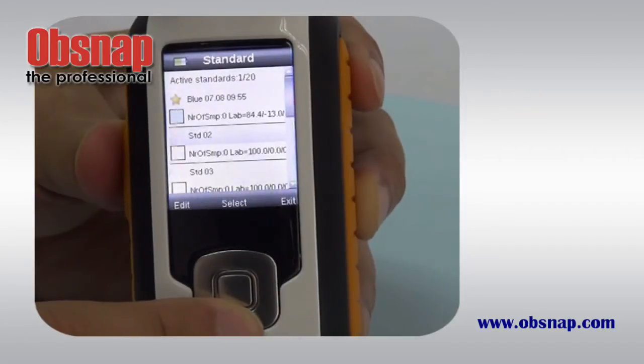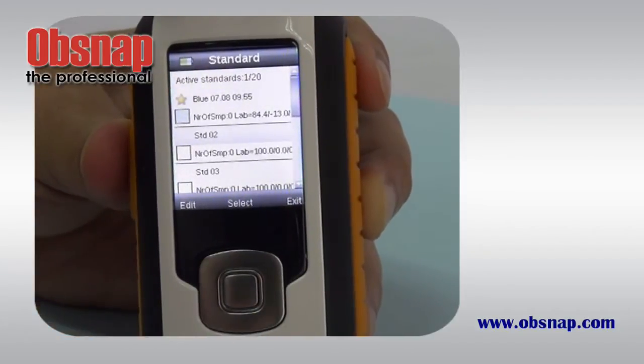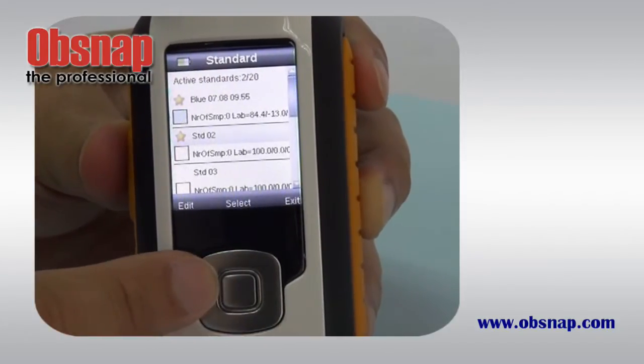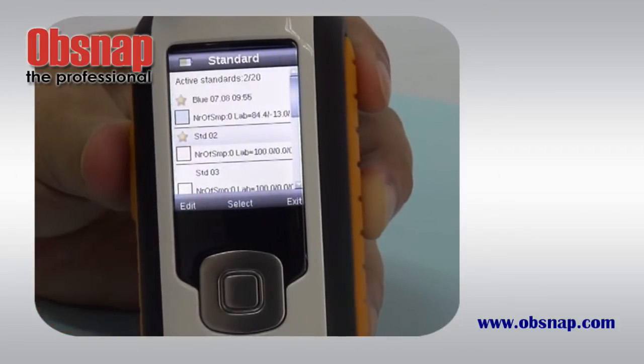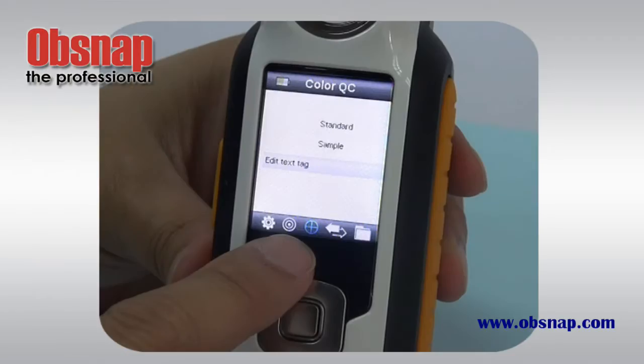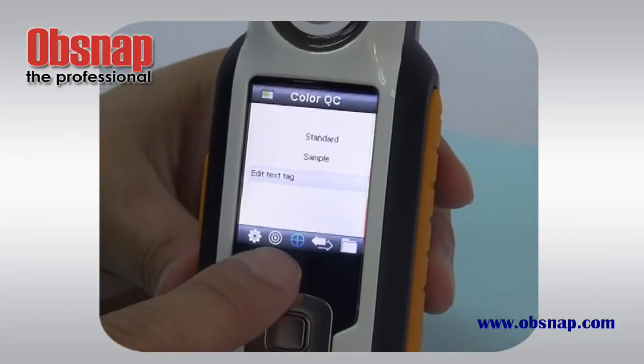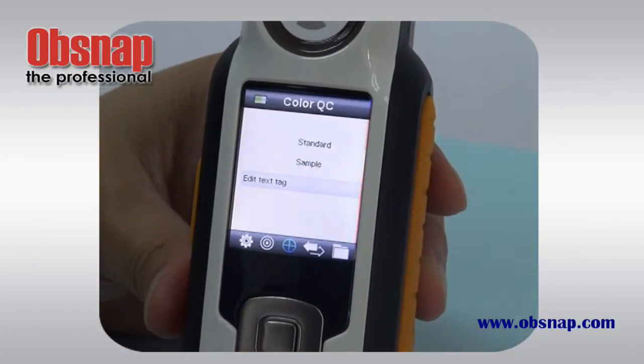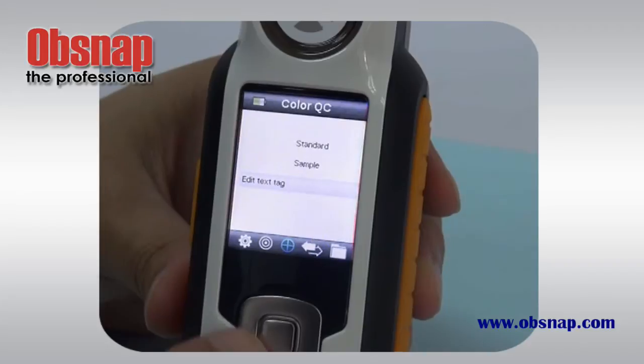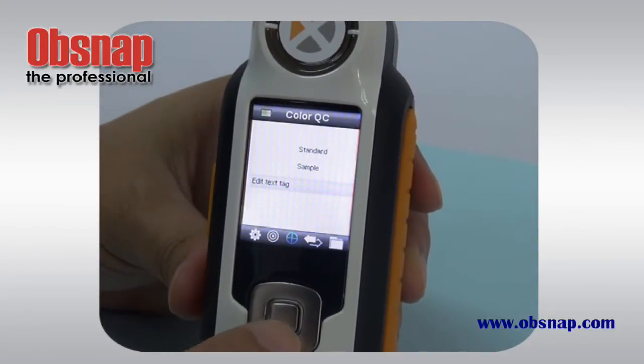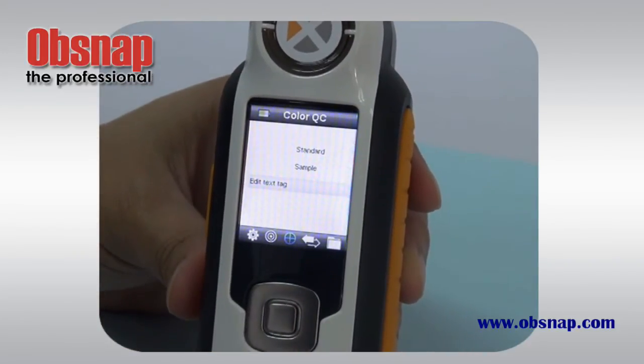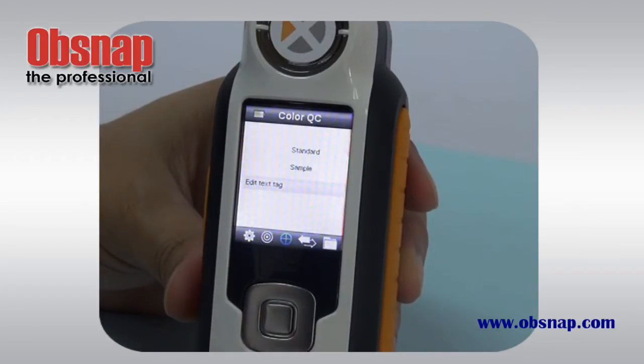For the subsequent standards you need to do, it is the same procedure: select it and then edit, and then you can measure onto the standard color. The third function is color QC. Color QC is actually for us to do comparison, color matching with our standard. Now we have one standard, which is blue, in our RM200QC.